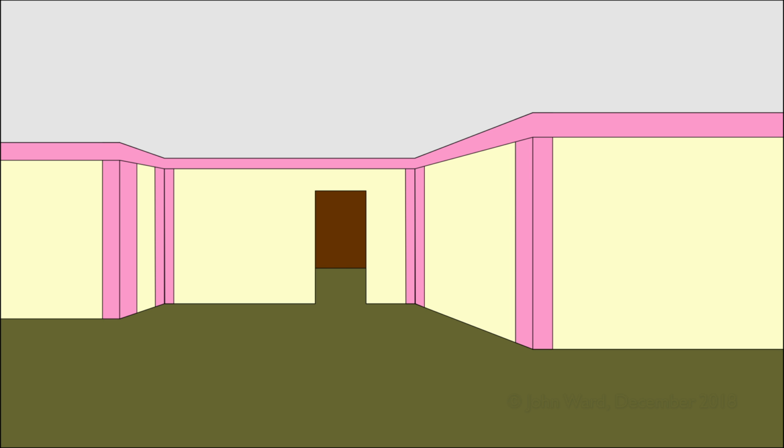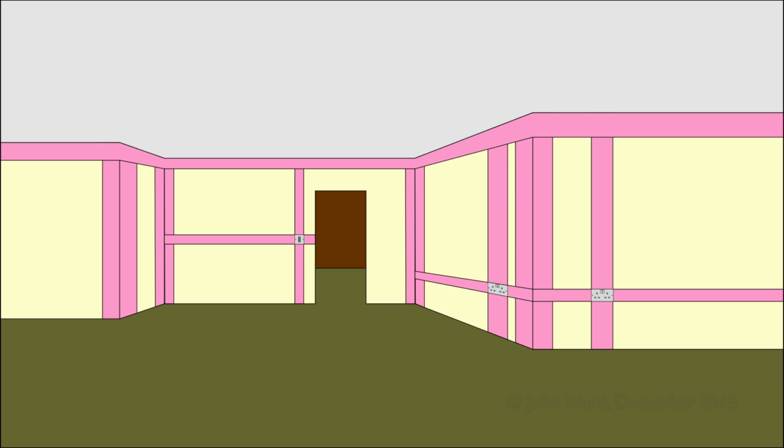They don't have to have anything necessarily attached to the wall or whatever. It's just where you can obviously run those things as needed. And then once you've actually fitted sockets, switches and other things on the wall, and that does include things like consumer units as well, each of those will then create its own zones horizontally and vertically, and those are the width or height of the particular item that you're fixing on the wall. So you end up with something like this.